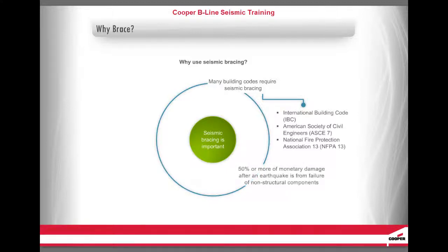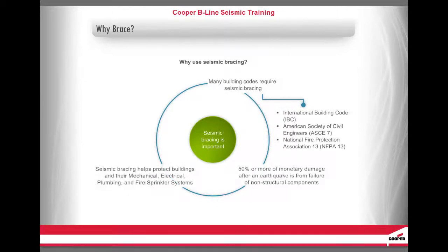Typically, 50% or more of monetary damage after an earthquake is from the failure of non-structural components. We've learned from historical earthquakes that seismic bracing helps protect buildings and their mechanical, electrical, plumbing, and fire sprinkler systems, otherwise known as MEP systems. Also, risk mitigation or insurance companies such as FM Global often drive the seismic bracing requirements.